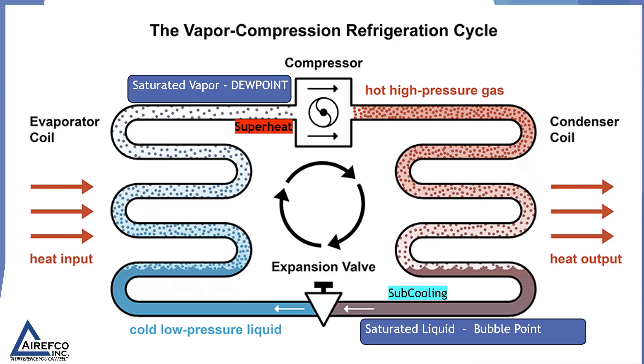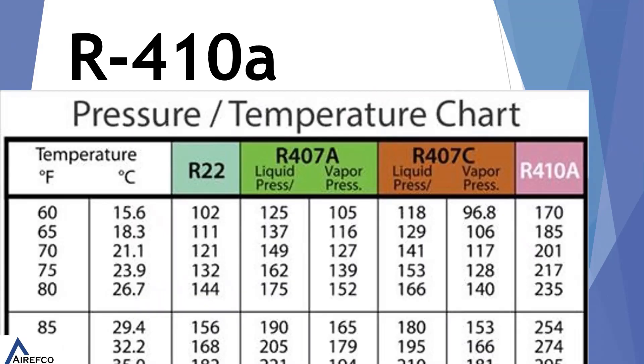The liquid at the end of the condenser is our subcooling point, and to take our subcooling reading we use the bubble point column on the PT chart. Many PT charts feature zeotrope blends with very slight glide, such as R410A, which we have long treated as a near-azeotrope mixture. Therefore, if there is a leak on an R410A system, it can be topped off without concern about different leak rates for the different refrigerants in the blend.